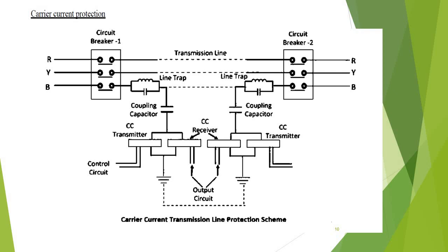The main elements of the carrier channel are a transmitter, a receiver, and coupling equipment followed by a line trap. The carrier current receiver receives the carrier current from the transmitter at the distant end of the line. This receiver converts the received carrier current into a DC voltage that can be used in the relay or other circuits to perform any desired function. The voltage is zero when carrier current is not being received.